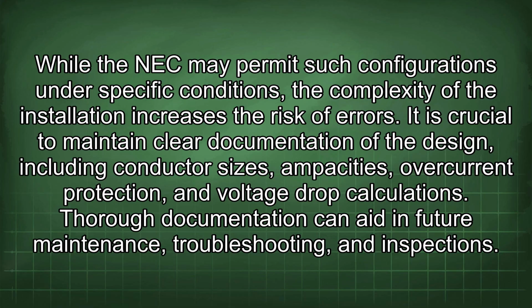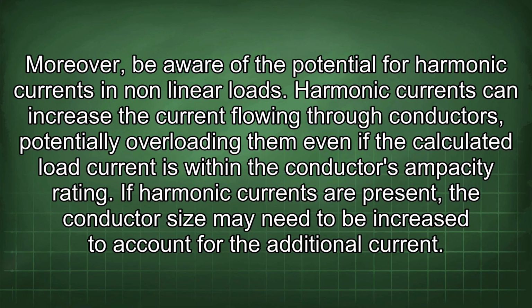It is crucial to maintain clear documentation of the design, including conductor sizes, ampacities, overcurrent protection, and voltage drop calculations. Thorough documentation can aid in future maintenance, troubleshooting, and inspections. Moreover, be aware of the potential for harmonic currents in nonlinear loads. Harmonic currents can increase the current flowing through conductors, potentially overloading them even if the calculated load current is within a conductor's ampacity rating.